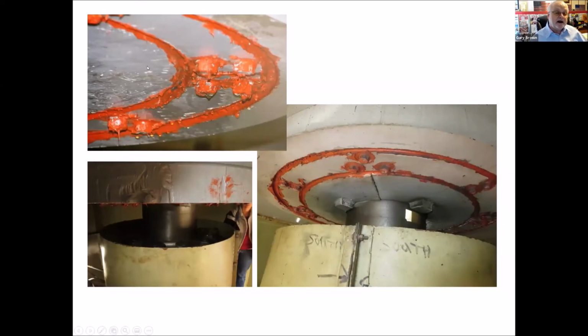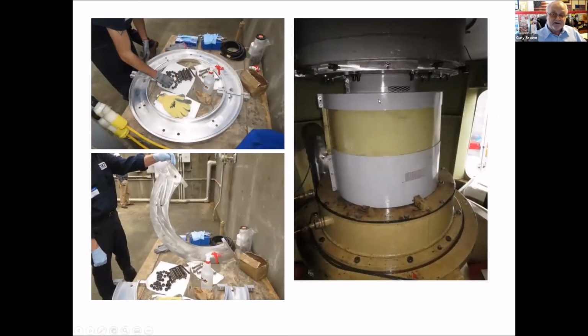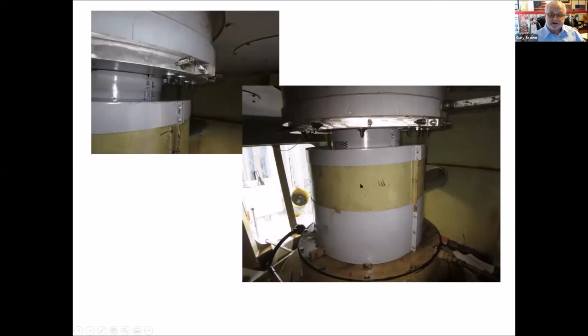We're going to make a clamp that has a hub seal that pushes up against here, covers everything, pushes up here. We'll change these bolts out one at a time, put a longer stud in with a nut, and then that stud will stick through our clamp after we get a bolt pattern. But we have to install a guard before we start doing that, because they don't want any nuts or whatever dropping down into this spinning shaft. That was a big concern. So over to the right here, you'll see where we had a fabricated additional guard put on, and then there was a clamp. We got the bolt patterns and installed it and sealed it, and that's what it looks like installed and sealed. I know that's kind of quick, but you guys can always come back to me.